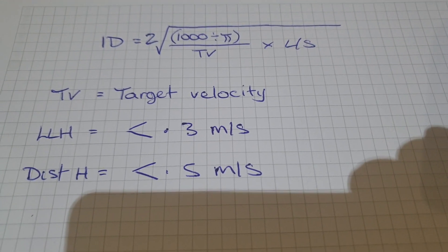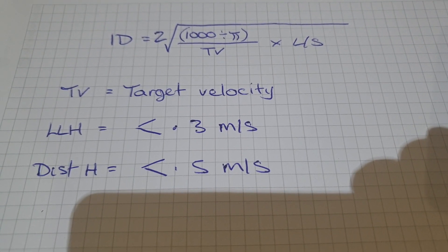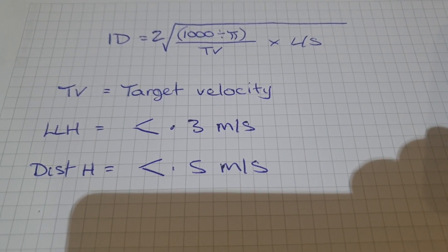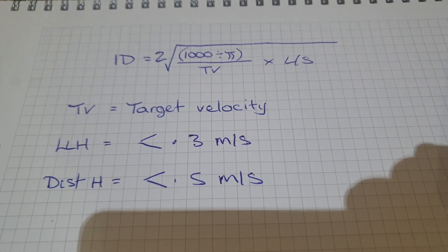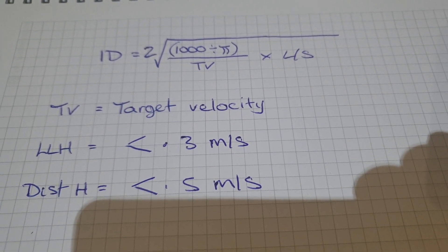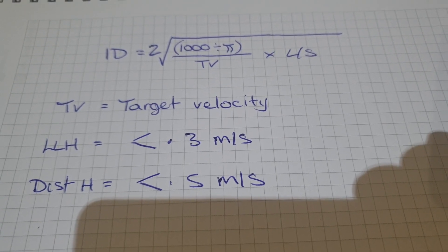So again, that formula is the internal diameter equals 2 times the square root of 1000 divided by pi divided by the target velocity multiplied by the liters per second. I hope that helps.